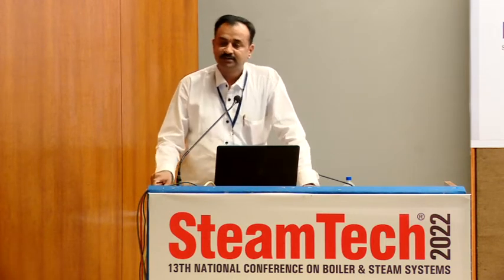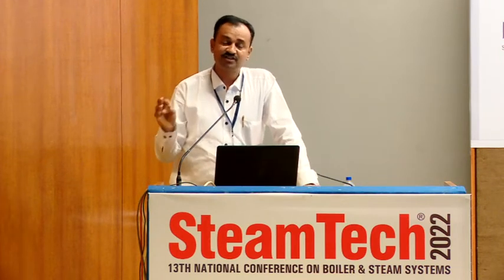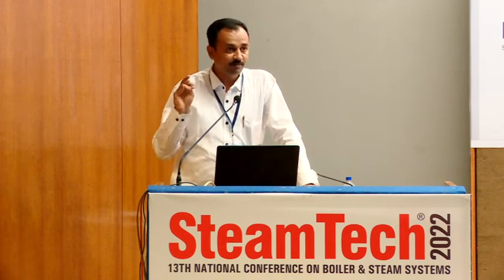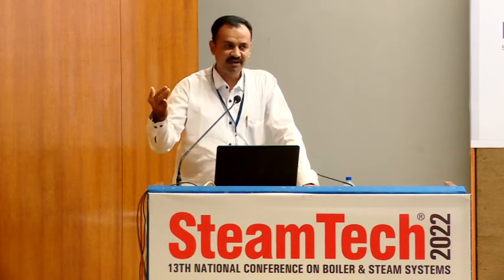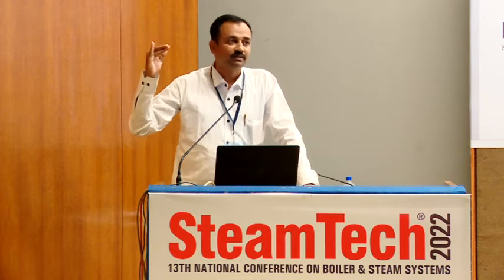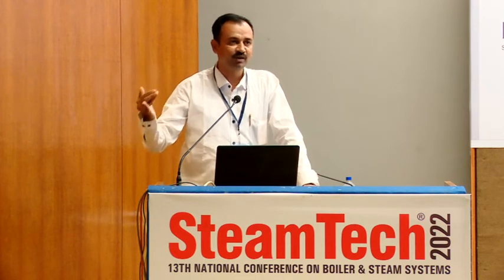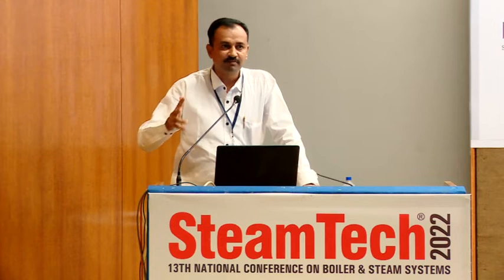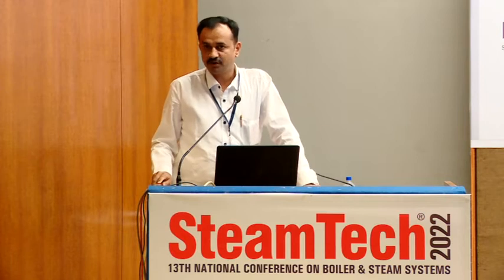What it requires from the user's point of view is that safety should be assured, so there should not be any downtime for that boiler. Efficiency should be optimum such that the user can get the best efficiency, not the rated efficiency, but at par with the best operating level of similar kinds of industry that have got the best efficiency. Productivity: of course, zero downtime of the boiler operation will ensure that the plant is operational continuously and there will not be any production loss. Environment: yes, the combustion parameters maintained well within limits, not disturbing much, no on-off cycles, and all that will lead to lesser emission, lesser CO formation and lesser SPM at the outlet, which will improve environmental efficiency also. All that put together, threaded into the operation and maintenance practices, will ensure that there will not be any unsafe situation and that efficient operation will always be available from the boiler house.